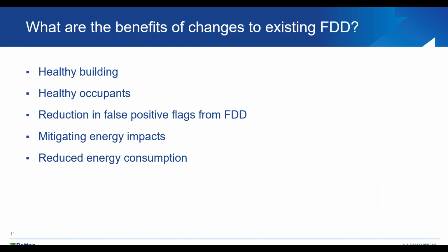What are the benefits of changes to the existing FDD? If you have an FDD system in the first place, you're obviously interested in the data and having a healthier building. So when we're looking at it under COVID conditions, we're looking at a healthy building and healthy occupants. How do we do that? We're looking at things like CO2 and percent outside air. We want to make sure that mold levels are kept down. You were doing it before COVID, and you want to continue to do that now. What happens with false positive flags? FDD provides a tremendous amount of information. How do we put that into a place where you can actually get valuable information before, during, and after COVID-19? How do we mitigate the energy impacts? There are some things that you would do beforehand. What can you do now, and what are you going to do later on in terms of reducing your energy consumption and reducing the energy impacts? Next slide, please.